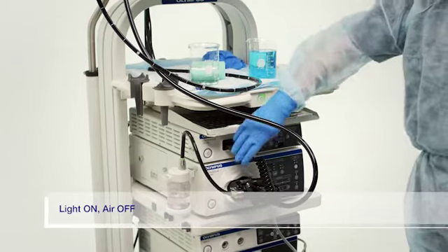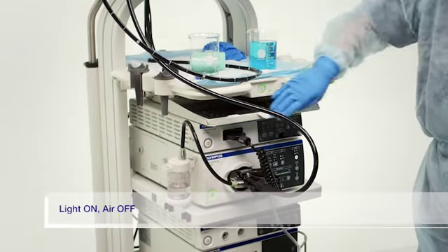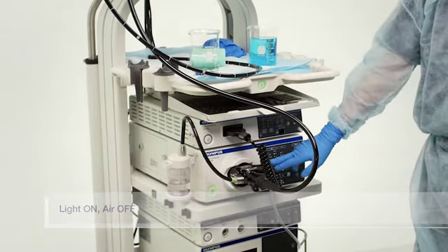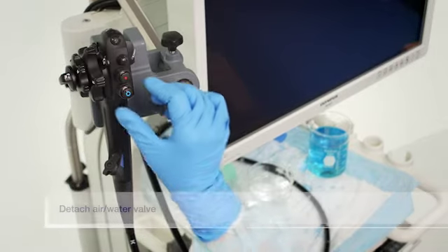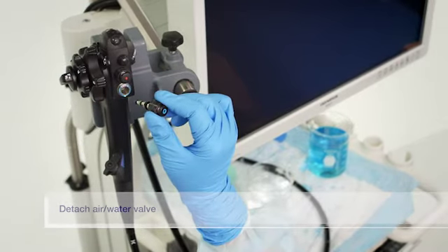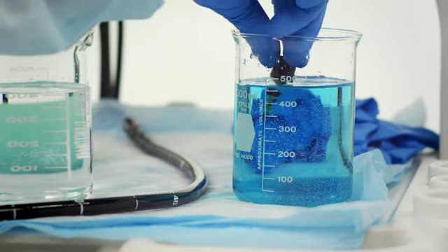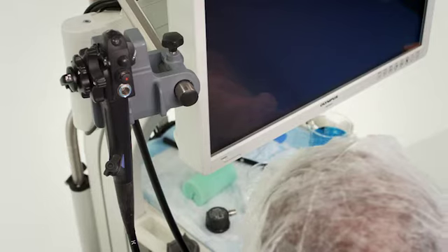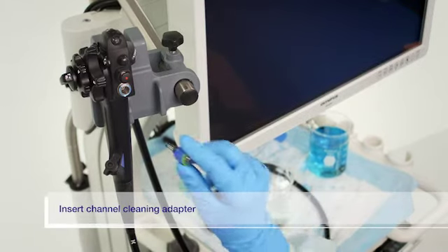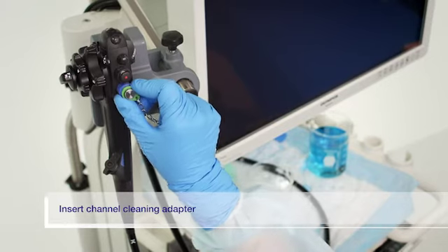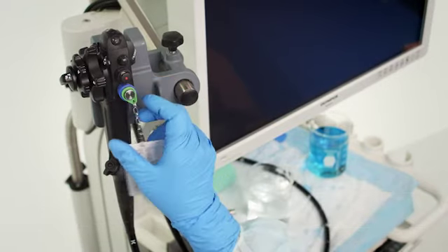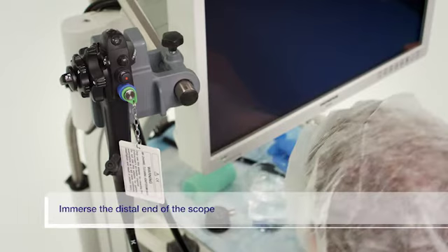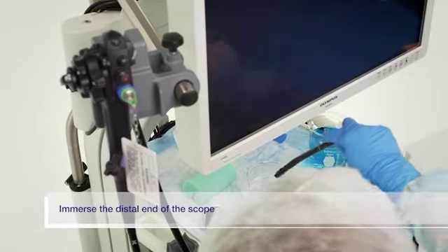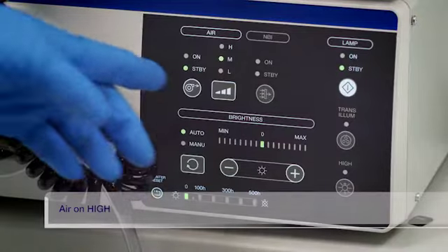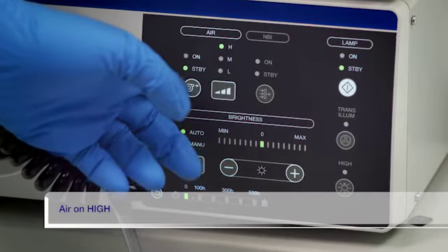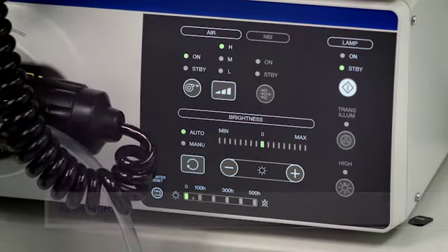Turn the light source on and switch off the airflow regulator. Detach the air-water valve from the endoscope and place it in the detergent solution. Attach the air-water channel cleaning adapter to the air-water cylinder of the endoscope. Immerse the distal end of the insertion section in the clean water. Then switch on the airflow regulator to maximum output.